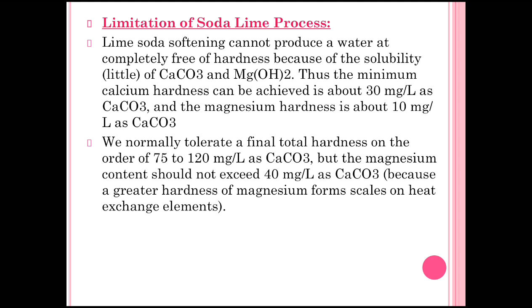Limitations of the soda lime process: the soda lime process cannot produce water completely free of hardness because of the solubility of calcium carbonate and magnesium hydroxide. The minimum calcium hardness achievable is about 30 mg/L as calcium carbonate and the magnesium hardness is about 10 mg/L as calcium carbonate. Normally the final total hardness in water is tolerated at 75 to 120 mg/L as calcium carbonate.